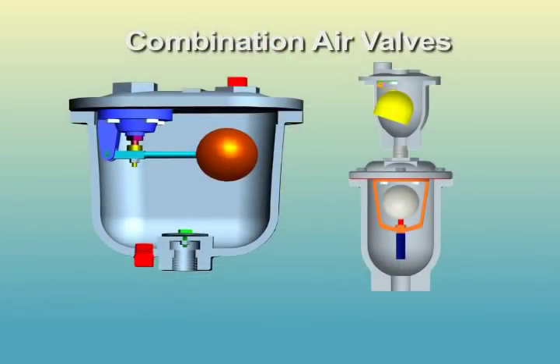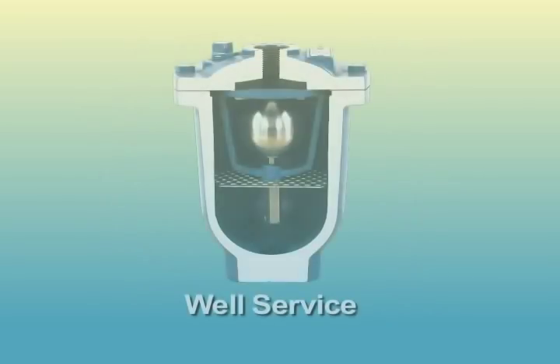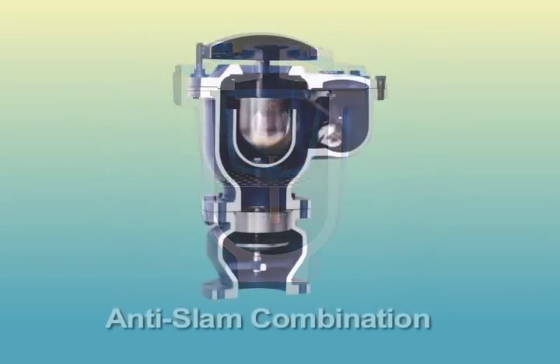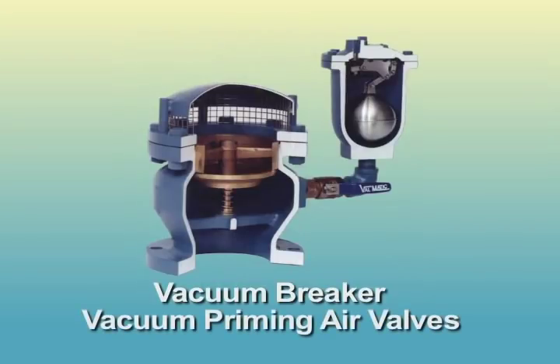Combination air valves are available in single body and dual body configurations. The single body configuration is more compact and economical. The dual body configuration provides two independent valves allowing access to the air release valve while the air vacuum valve continues to protect the pipeline. The dual body valve also provides a much wider range of sizing options. There are a number of different types of air valves including well service, anti-slam combination, ventilation, vacuum breaker, and vacuum priming valves.